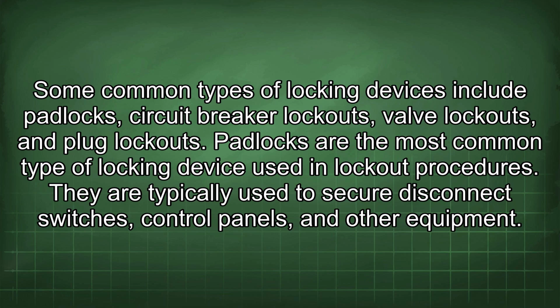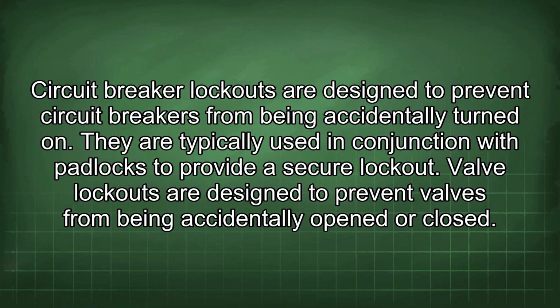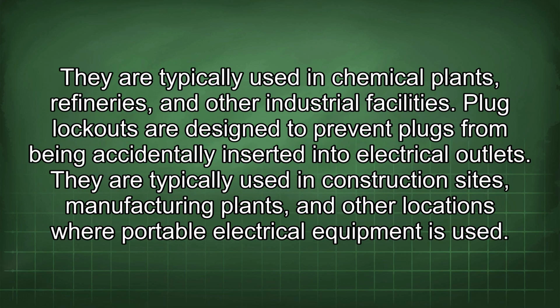Padlocks are the most common type of locking device used in lockout procedures. They are typically used to secure disconnect switches, control panels, and other equipment. Circuit breaker lockouts are designed to prevent circuit breakers from being accidentally turned on. They are typically used in conjunction with padlocks to provide a secure lockout. Valve lockouts are designed to prevent valves from being accidentally opened or closed. They are typically used in chemical plants, refineries, and other industrial facilities. Plug lockouts are designed to prevent plugs from being accidentally inserted into electrical outlets. They are typically used in construction sites, manufacturing plants, and other locations where portable electrical equipment is used.